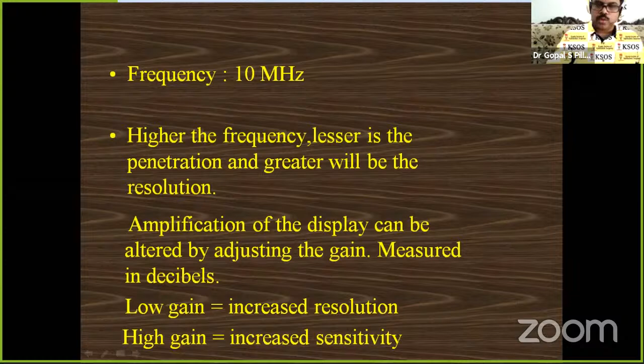Amplification of the display can be done by adjusting the gain. Low gain means increased resolution. The resolution power is much higher. High gain means there will be a lot of grains, but it will pick up even smaller problems. So there is increased sensitivity. And that is how we do an ultrasonography.